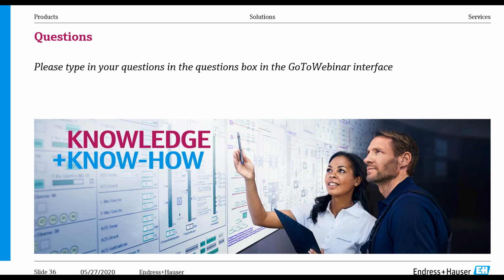All right, thank you. Another one for you, Jason. We've got a question asking about price-wise and the advantages compared to a Coriolis flow meter in the same application. Okay, so price-wise, as you get bigger in sizes, Coriolis meters get quite big, and there's a lot of material there. So at typically 1 to 2 inch, both of them are about in the same price range. But as you get to 3 inch and bigger, the price advantage goes to the ultrasonic meter. We have a lot less material of construction, so it's priced accordingly. With the ultrasonic meter, you also have no pressure drop. That's one of the disadvantages of the Coriolis, and you also need a certain amount of pressure. They can't go down to the low pressures that we have with the ultrasonic meter.